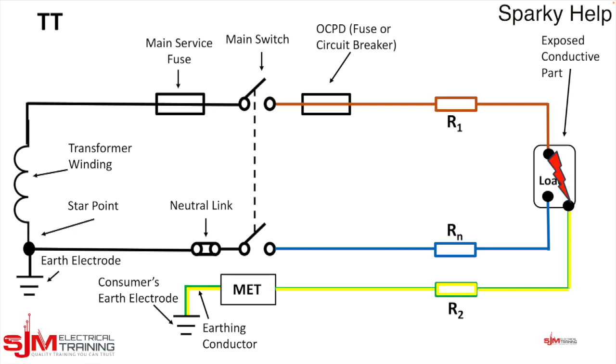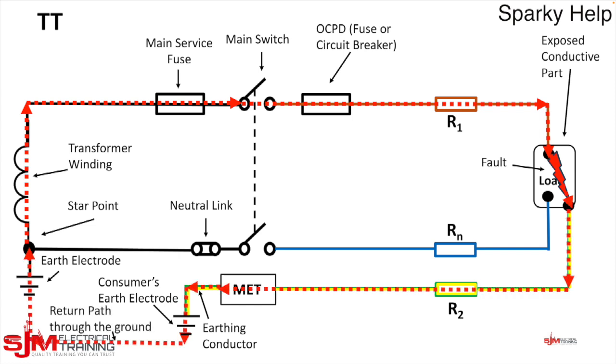Let's introduce the fault and label it as so. We want a fault of negligible impedance. So there's our fault, and now current will flow, and it will flow in this direction, down through there, and then through the earth. Through the ground is the return path. So there we have the earth fault loop path for a TT installation.